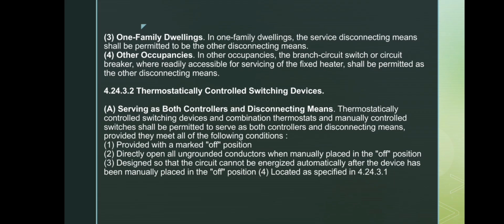Now we move to Article 4.24.3.2, thermostatically controlled switching devices. When a thermostat switch can act as a disconnect: thermostats or combination thermostat switches may serve as both the controller and the disconnect if they meet all these conditions. They must have a clearly marked off position. When switched off manually, they must open all ungrounded conductors. Third, the circuit must not turn back on automatically after being switched off.